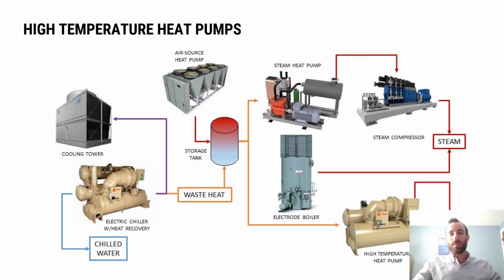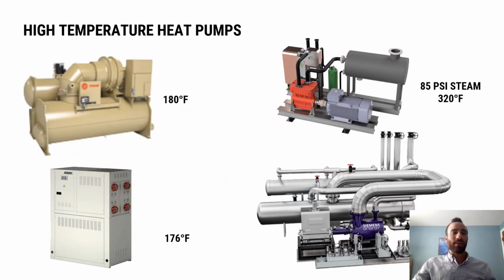Speaking of high hot water temperatures, another exciting innovation we're working with today is high temperature hot water heat pumps and even heat pumps that can make steam. This is particularly important in the retrofit world, where we often can't convert a building fully to low temperature hot water, where we don't have the luxury of time to convert all of our systems to low temperature 120-degree hot water that works with conventional heat pumps. And instead, we're retrofitting systems with high lift centrifugals like you see on the top left, and even heat pumps, which is really exciting, that can make medium pressure steam without fossil fuels for process uses and other types of applications.